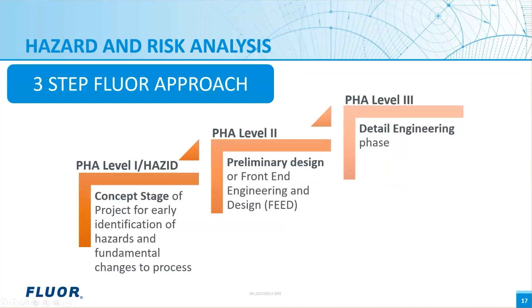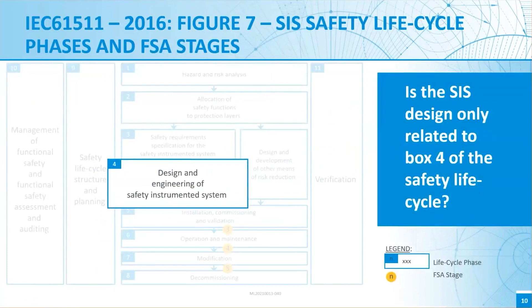The details were covered in the last webinar, but to answer it here: basically the SIS should operate completely if it involves the movement of a valve. For example, an 8-inch valve typically takes a certain amount of time, like 10 to 15 seconds, based on the configuration. Of course, you can have quick closing or opening valves to shorten that.